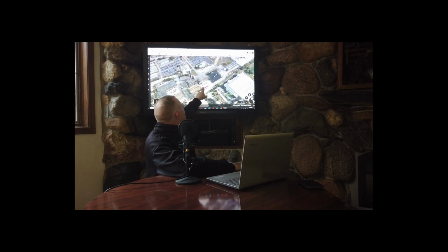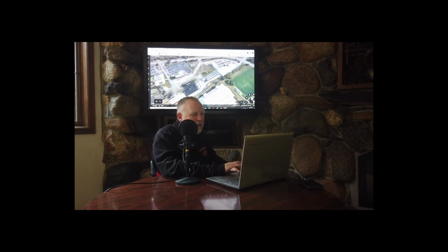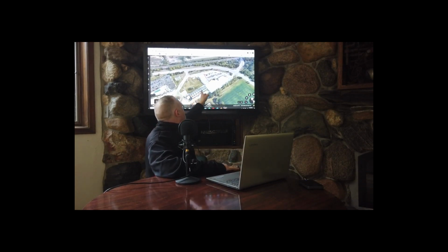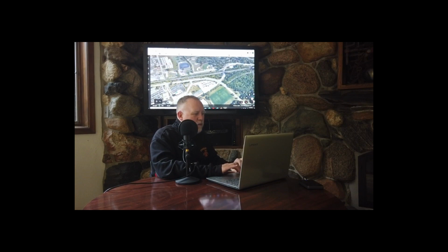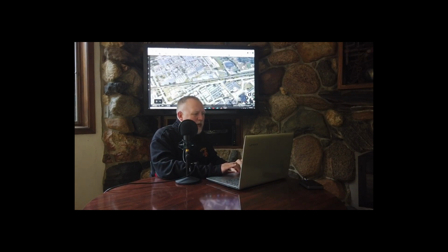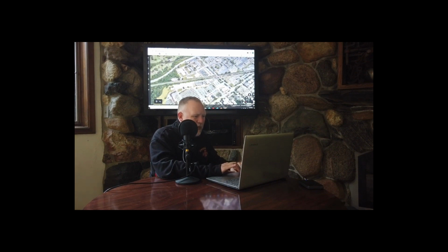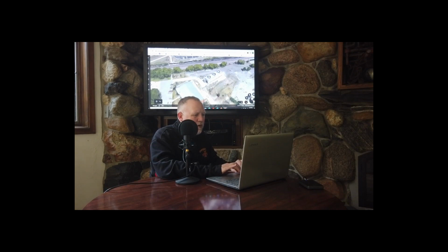Okay, I want to say these are the gas-fired, and then the chiller plant is over here, and I think that's the coal-fired part. But all of the heat from this is rejected right here, this massive string of cooling towers right along there. And at one point, Iowa State was running out of cooling capacity, and instead of making that system bigger, they decided to add a second cooling plant and connect the two over here.